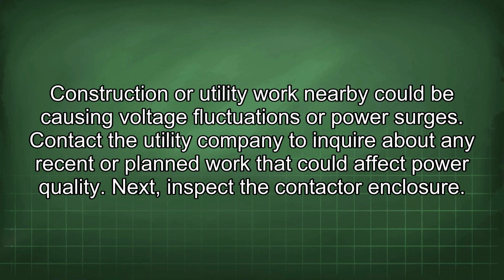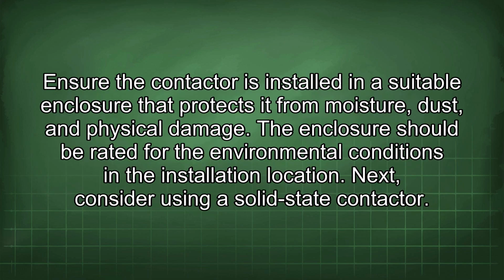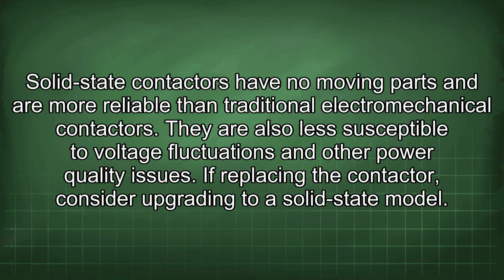Next, inspect the contactor enclosure. Ensure the contactor is installed in a suitable enclosure that protects it from moisture, dust, and physical damage. The enclosure should be rated for the environmental conditions in the installation location. Next, consider using a solid-state contactor. Solid-state contactors have no moving parts and are more reliable than traditional electromechanical contactors. They are also less susceptible to voltage fluctuations and other power quality issues. If replacing the contactor, consider upgrading to a solid-state model.